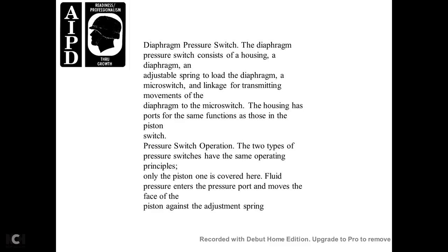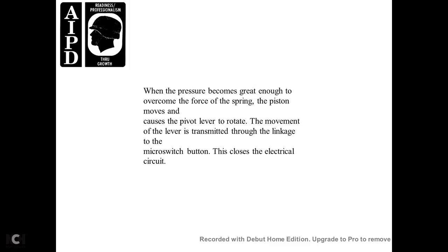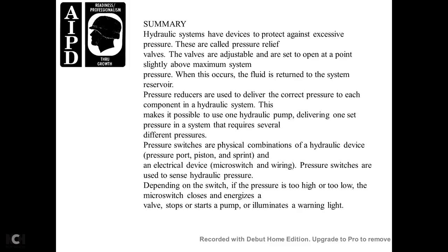Pressure Switch Operation. The two types of pressure switch operate on the same principle; the only difference is that one uses a piston and the other a diaphragm. Fluid pressure enters the pressure port and moves against the face of the piston against the adjusting spring. When the pressure becomes strong enough to overcome the force of the spring, the piston moves, causing the pivot lever to rotate. The movement of the lever is transmitted through linkage to the micro-switch button, which closes the electrical circuit.